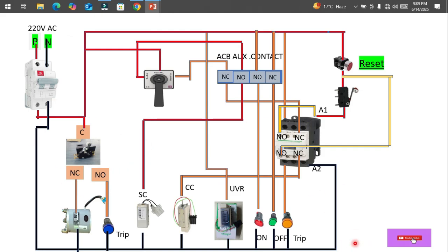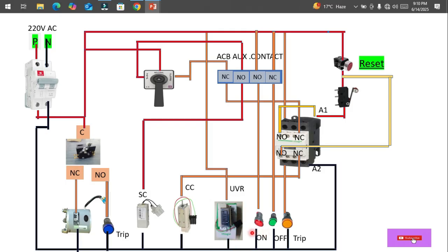Now let's trace the neutral wherever required. The neutral is from the MCB, and from the output of this MCB it is going to the universal motor, then to the spring charge indicator to monitor whether the spring is charged or not, then to the shunt coil, then to the closing coil, then to the under-voltage relay, and then to the on, off, and trip indicators, and finally also to the auxiliary contactor terminal A2. This is a 220-volt operated contactor.